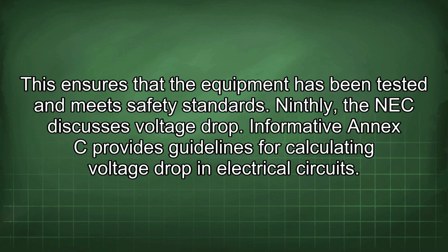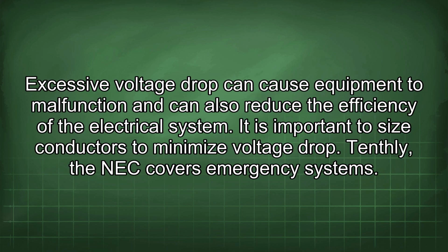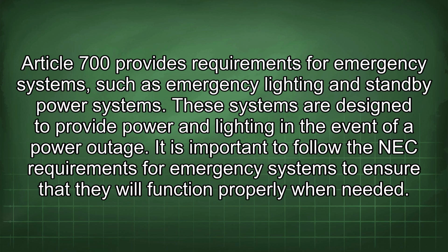Ninthly, the NEC discusses voltage drop. Informative Annex C provides guidelines for calculating voltage drop in electrical circuits. Excessive voltage drop can cause equipment to malfunction and can also reduce the efficiency of the electrical system. It is important to size conductors to minimize voltage drop. Tenthly, the NEC covers emergency systems. Article 700 provides requirements for emergency systems, such as emergency lighting and standby power systems. These systems are designed to provide power and lighting in the event of a power outage. It is important to follow the NEC requirements for emergency systems to ensure that they will function properly when needed.